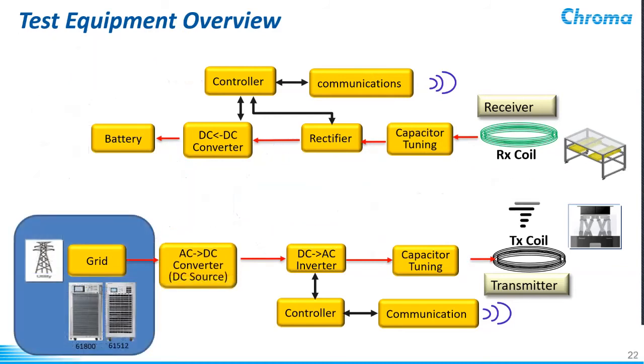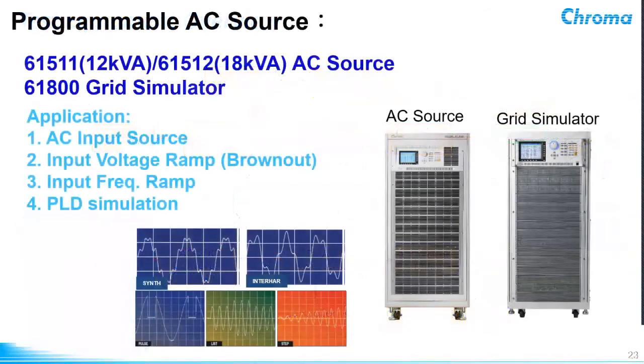Start with the grid simulation. Chroma has the AC grid simulator plus the AC source to simulate your grid power from single phase to 3 phase. As I mentioned, Chroma has an AC source and grid simulator to generate an AC waveform and to accommodate all of the AC source testing requirements to simulate your grid power, and that will validate your input frequency ramp and also generate some harmonic distortion.